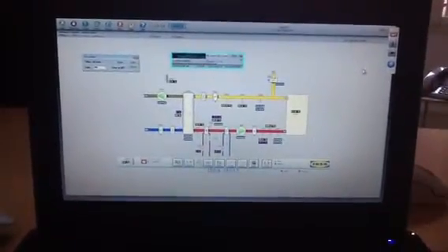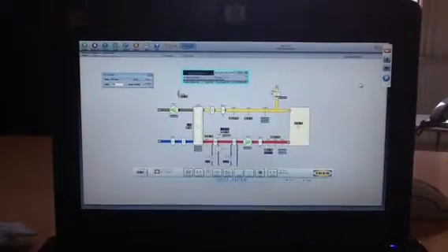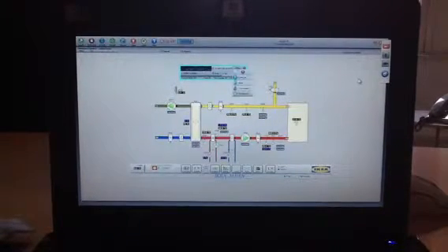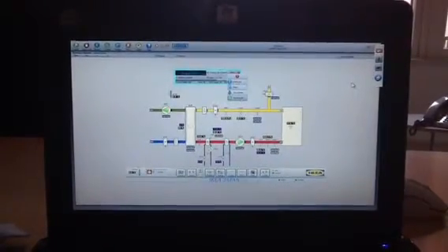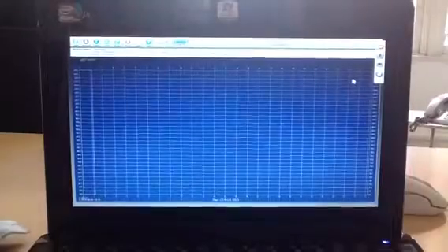If you set the limit to 100 running hours, then you will have an alarm when you are at 90% of that level. So then you would know it's time for changing the wheel belts or anything else. And the last one is the trend curve, and for a fan there is no trend curve. That's only for reading values, for measurements and things like that.